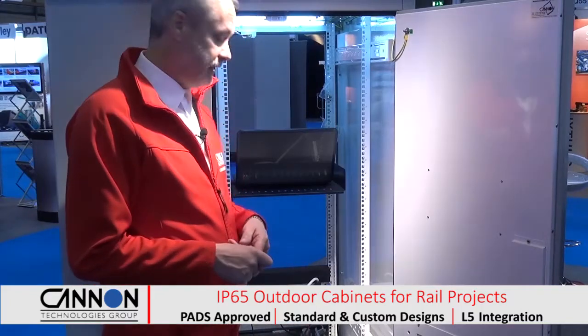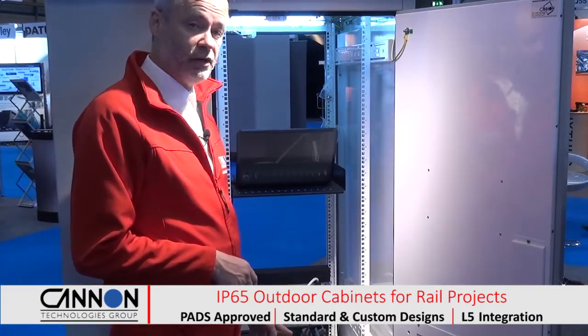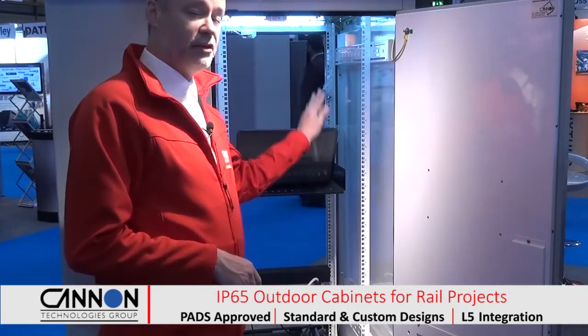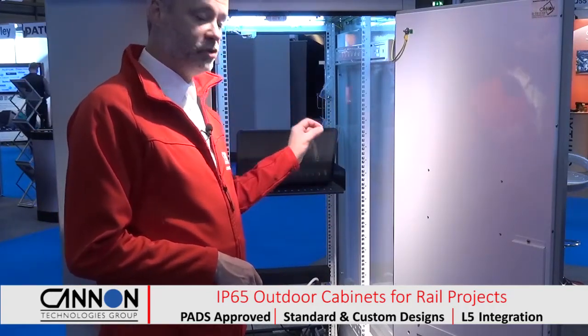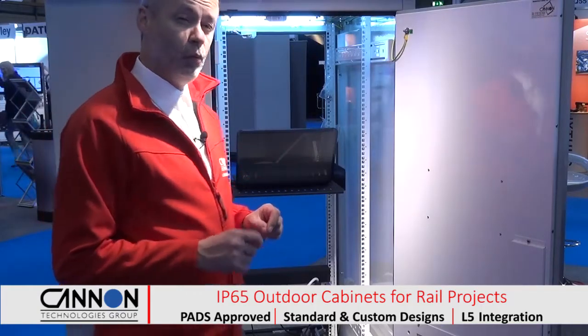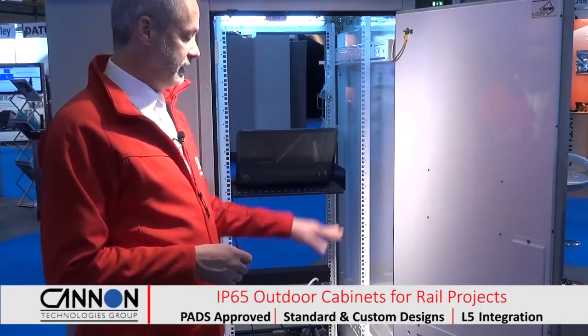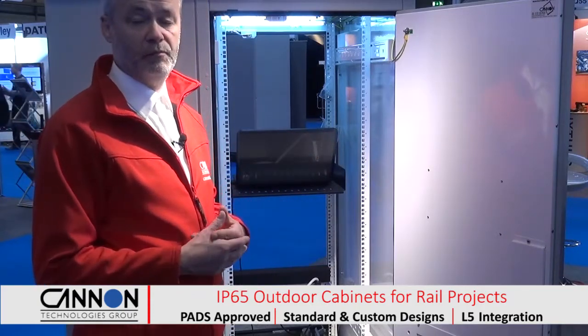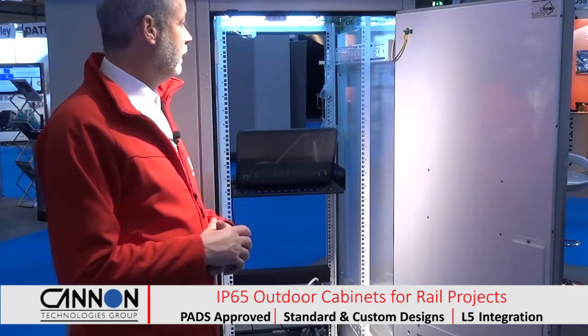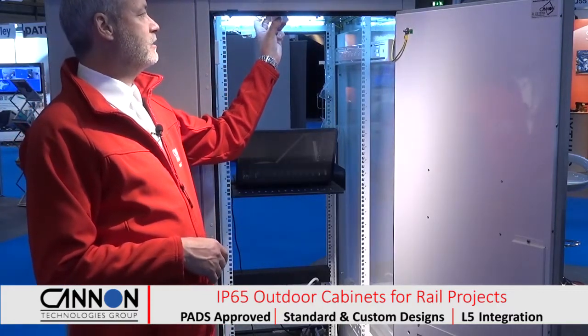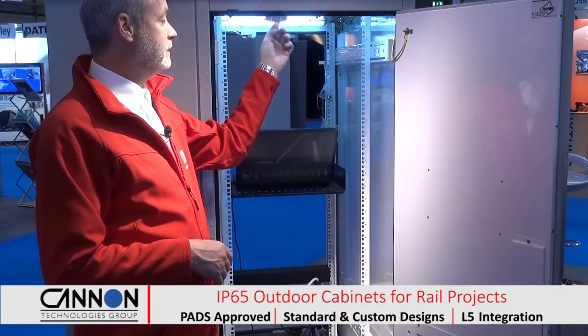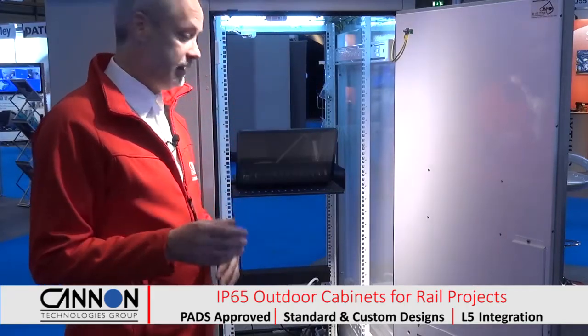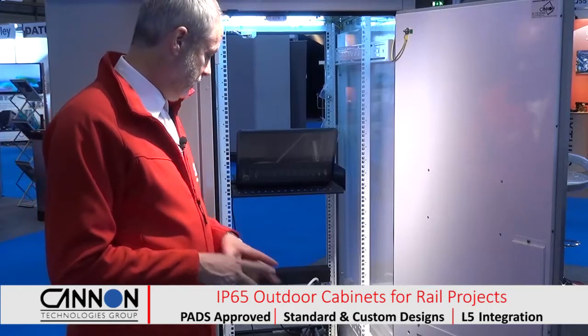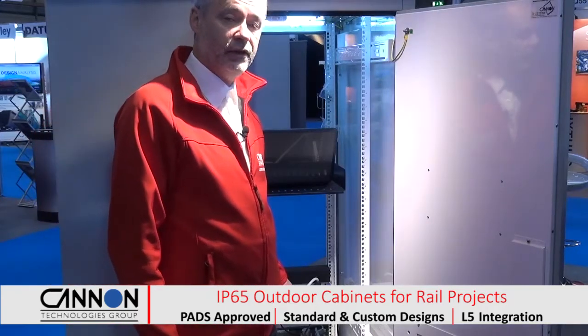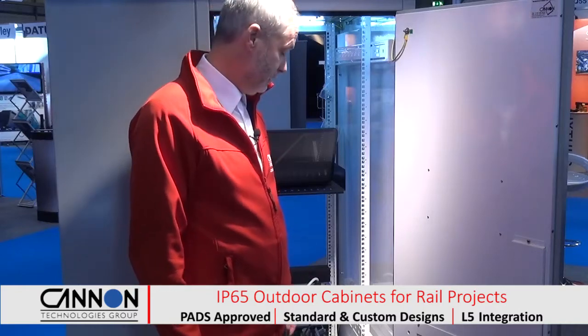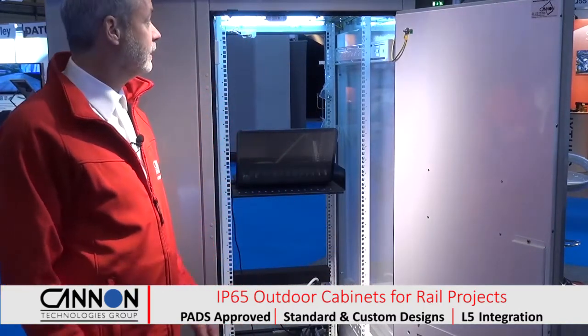For the heater, we do some calculations to work out the size that's required. We take calculations about how much electronic equipment is fitted in there and how much heat is produced by that equipment, and then we calculate the difference required to bring the cabinet up to temperature during minus temperatures. Again, you can see here another sensor which allows us to operate the door light, so you can light the cabinet up and ensure good access during servicing, etc. And down in the base there is the main earthing point where the contractor would bring in the main earth, which is then distributed between all of the different panel work.